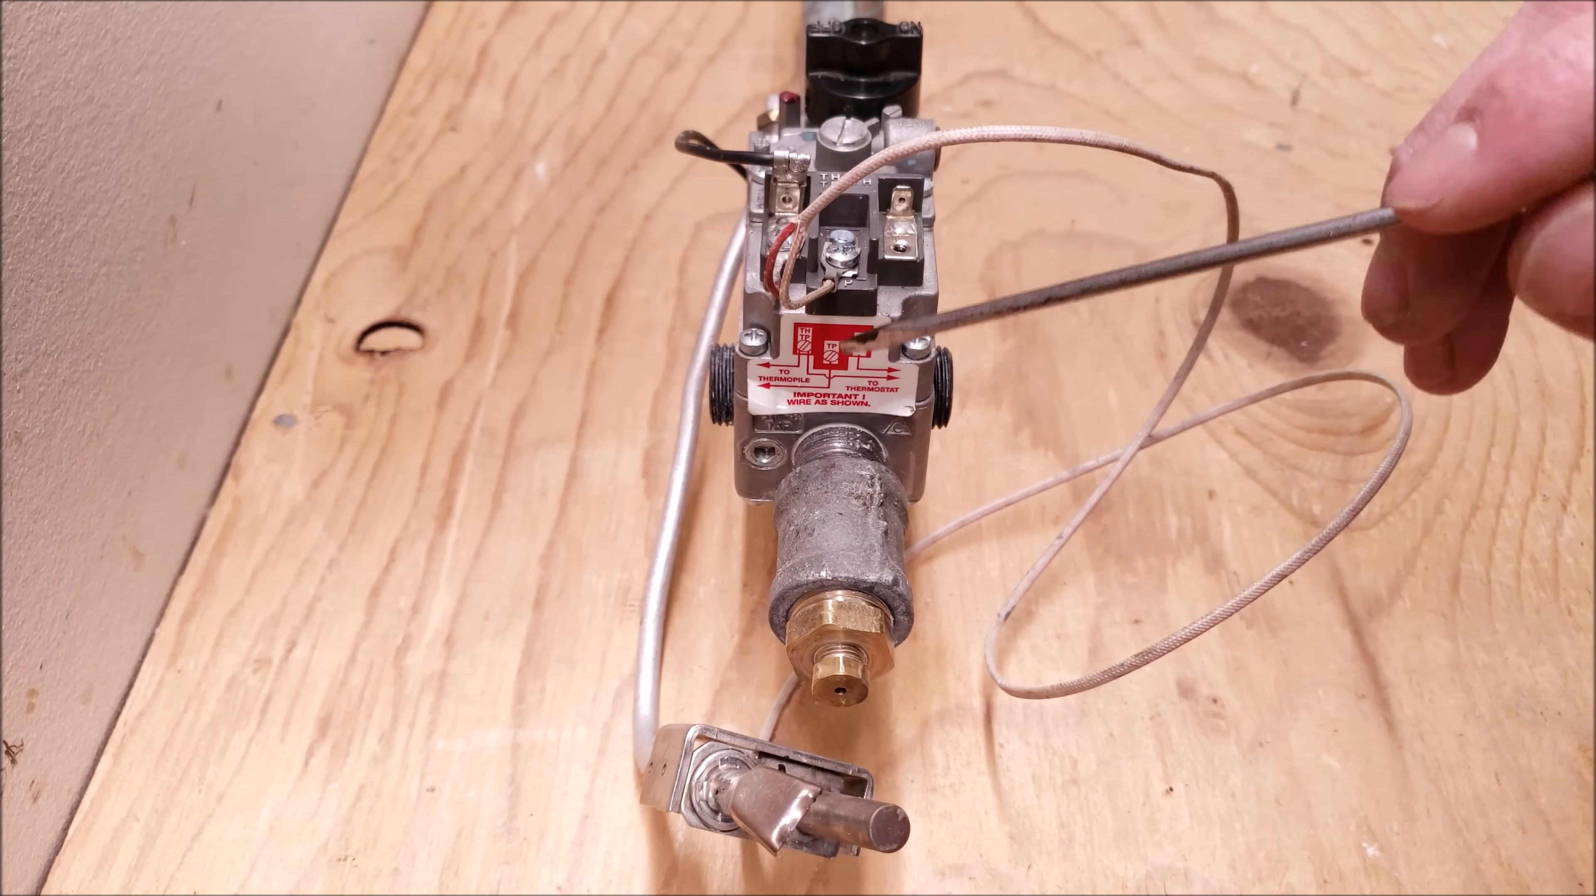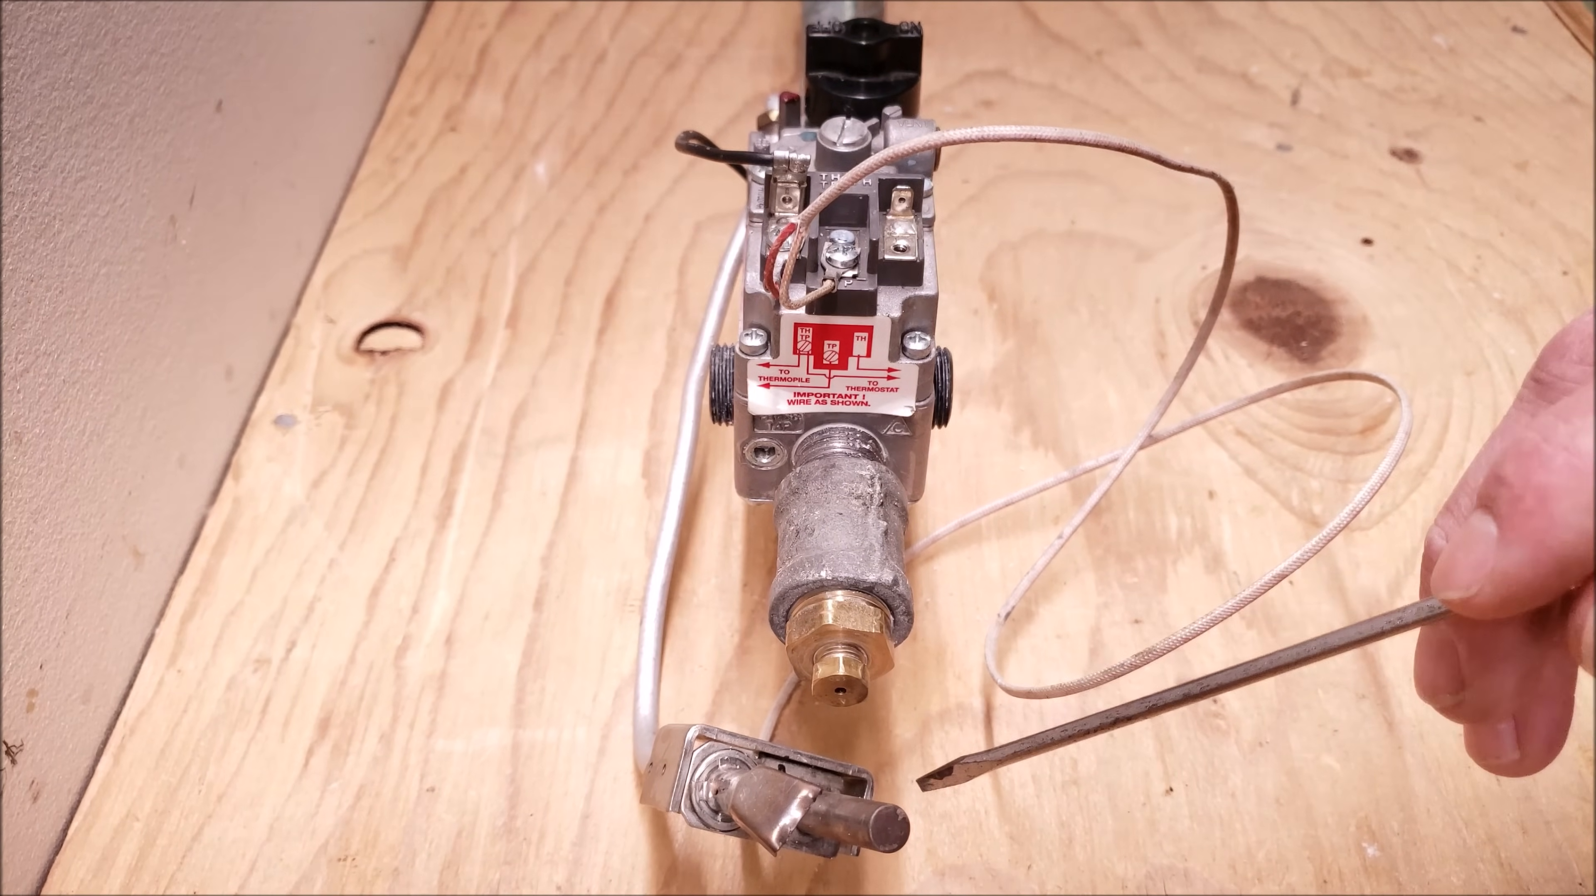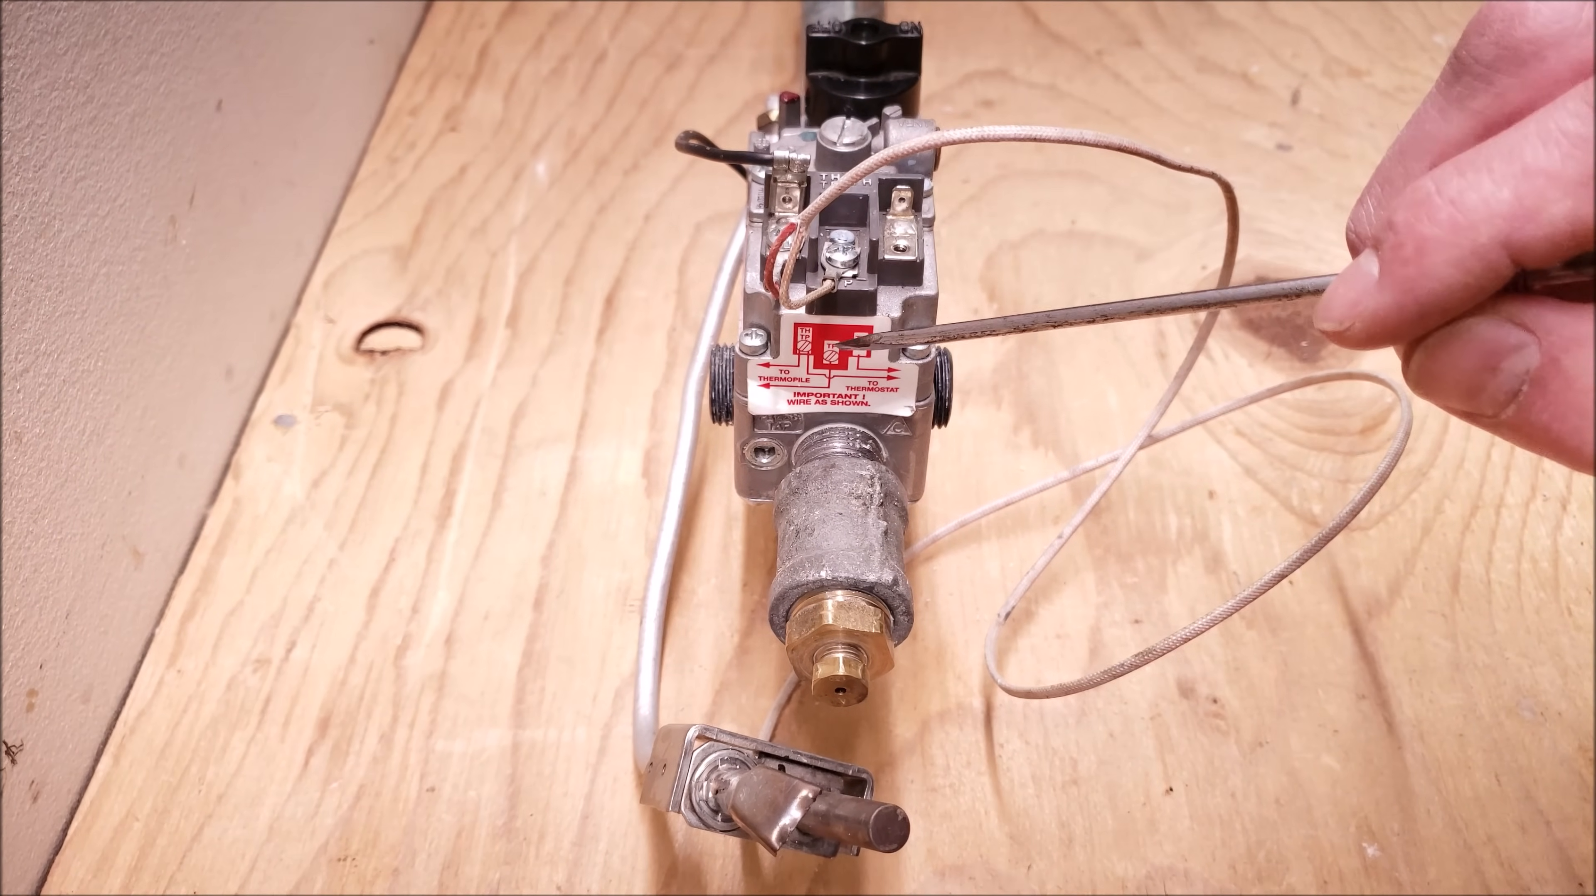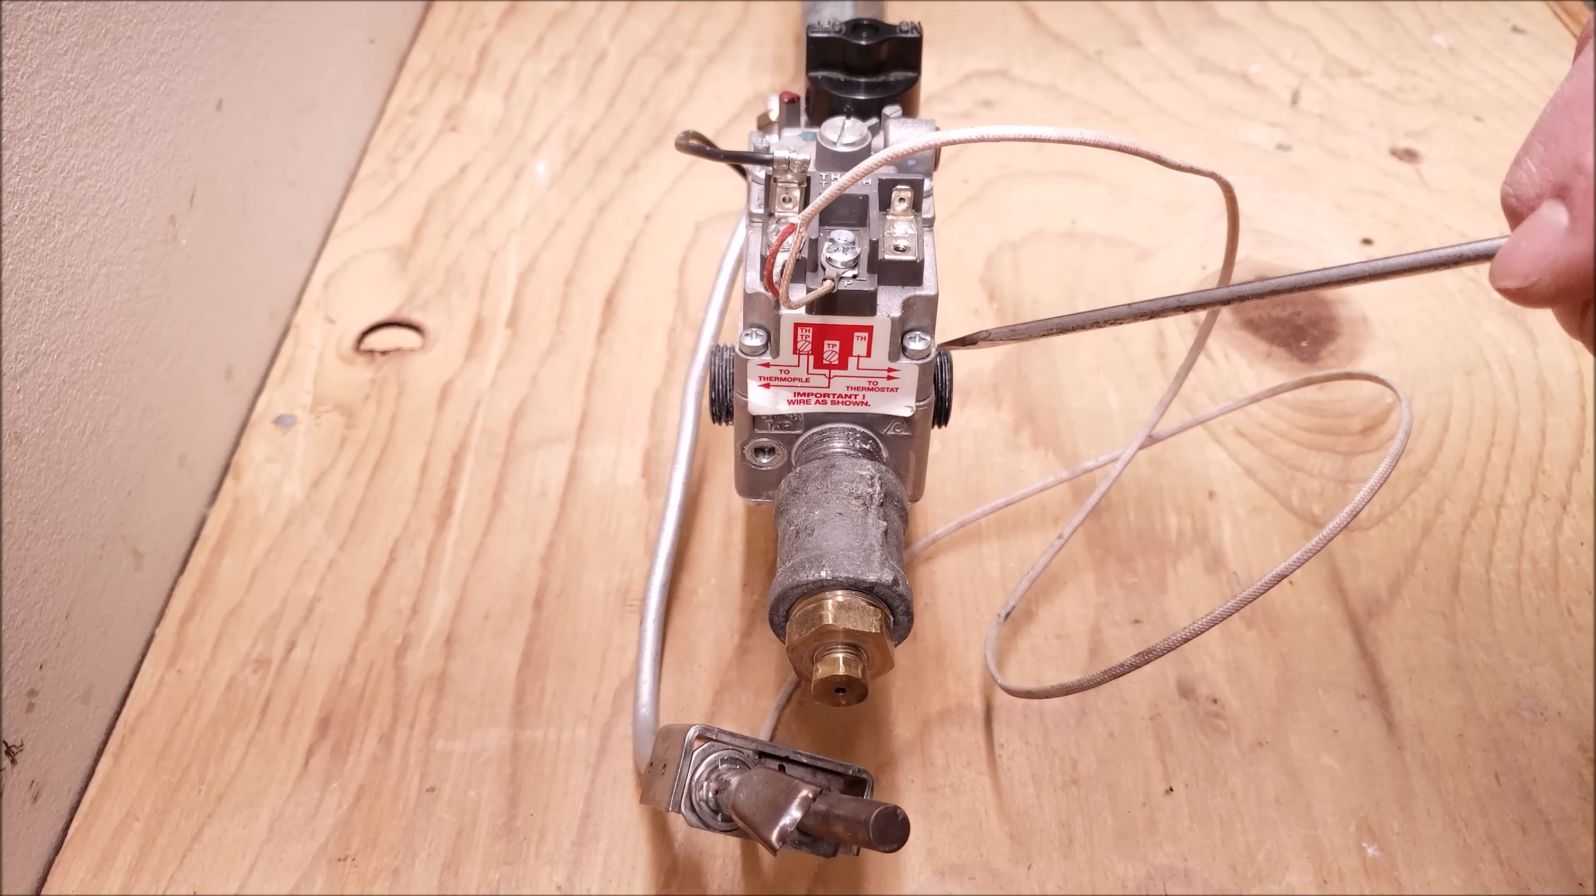So this gas valve is not powered with any AC voltage, we're just using the millivolts generated at the thermopile due to the pilot flame heat and that's enough voltage to hold open the pilot solenoid as well as to power the main gas valve solenoid.